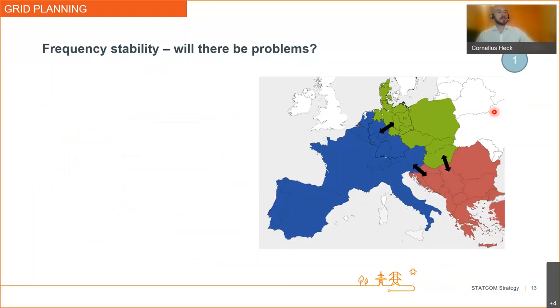I've already stated that the reactive power problem is not the only problem that we are facing. We might also face some frequency stability problems, but what are these problems going to look like? So first things first, the typical outage of one huge power plant, so for the central European grid, that would be 3 gigawatts, that is the reference case, will not be a problem for RoCoF situations in the future. So RoCoF, that is rate of change of frequency, so the gradient of the frequency just after an event has occurred. But maybe there are other problems that might cause problems.